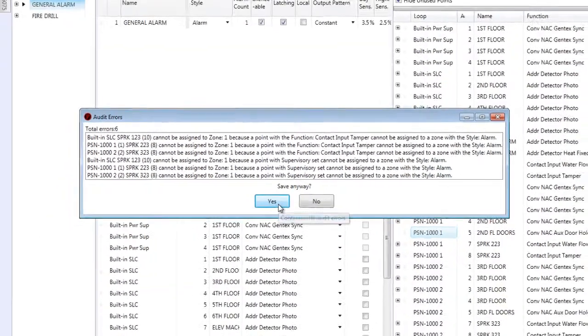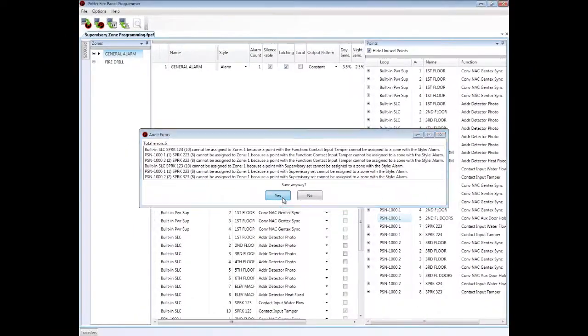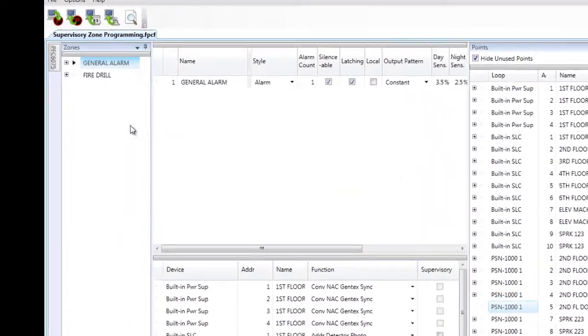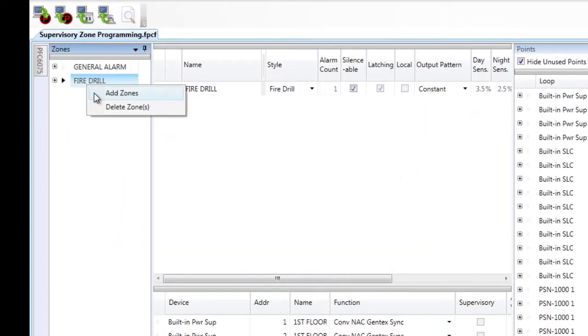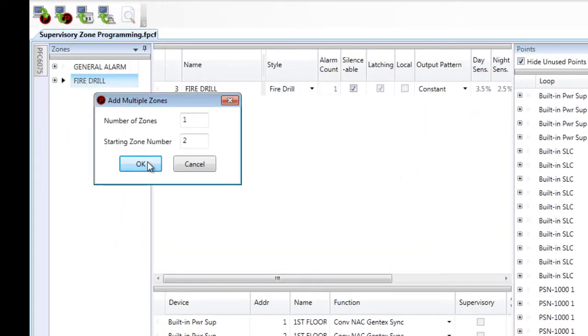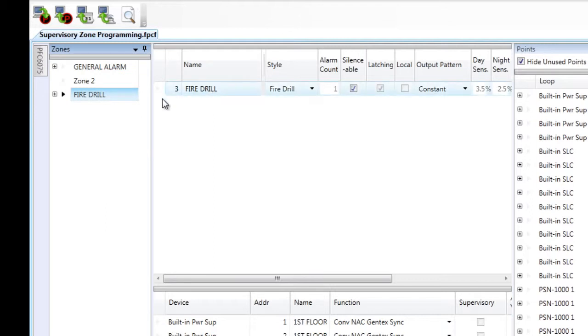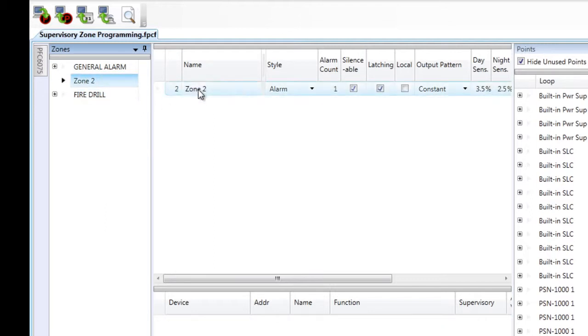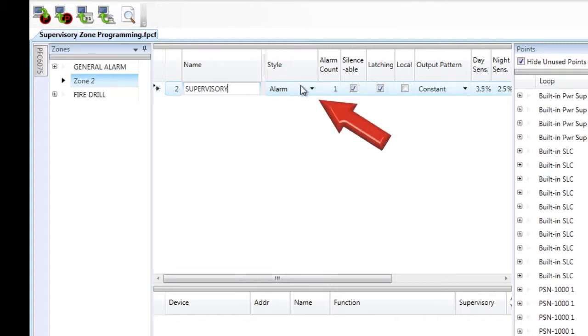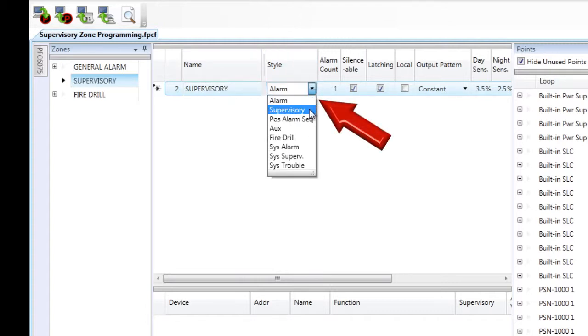So what I need to do is I can save this, but it won't let me download, is I need to create a supervisory zone. So I'm going to add one zone. I'm going to call it supervisory. You can call it whatever you'd like. And the important thing here is to make it style supervisory.